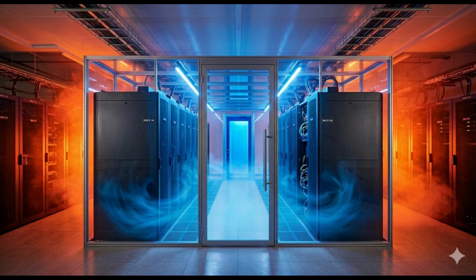If the processors start doing heavy computations, the servers get hot, their internal fans spin up, and the volume flow demand of the rack spikes. So the room has to be designed to feed that demand perfectly, which is why we use aisle segregation. Yes. You arrange the floor plan into alternating rows, cold aisles and hot aisles.